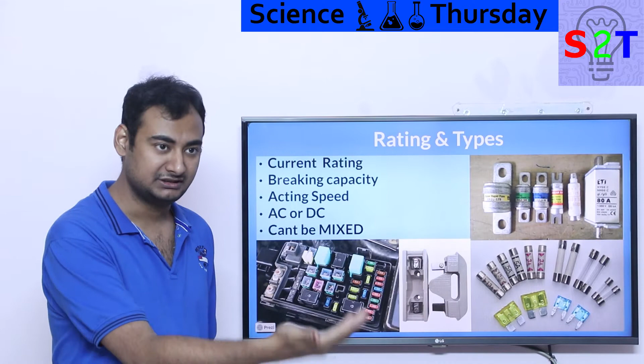But what about semiconductor equipment? Let's say your TV has a fuse. That one's supposed to be as fast as possible, because semiconductors are not resilient at all, so you need idiotically fast acting speed. That's why acting speed also cannot be mismatched. If you put a slow acting fuse on a semiconductor device, the semiconductor is toast. If you put a fast acting fuse on an inductive load, it's going to trip every time you turn it on. So fundamentally you have to take that into consideration.